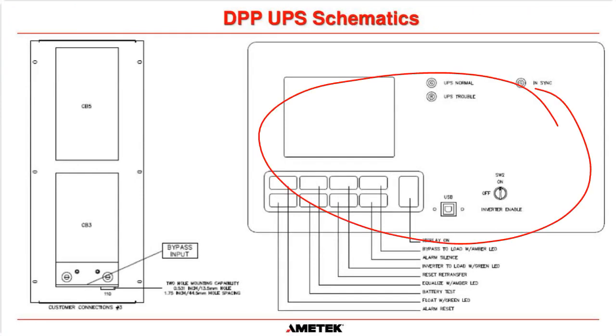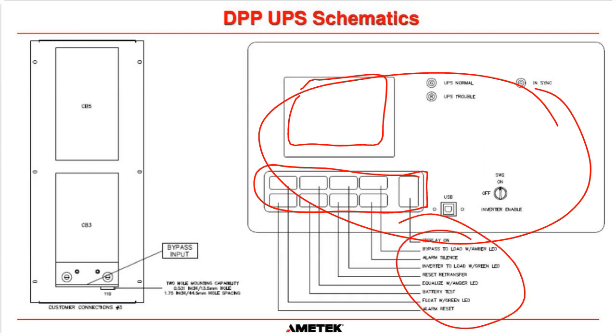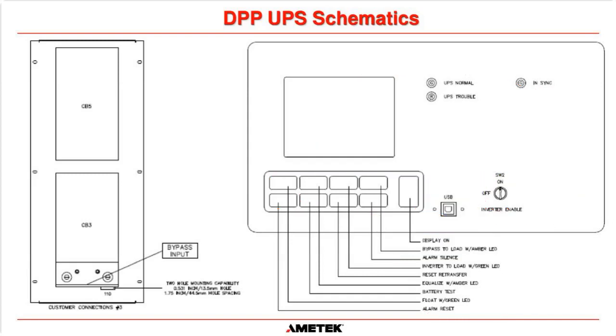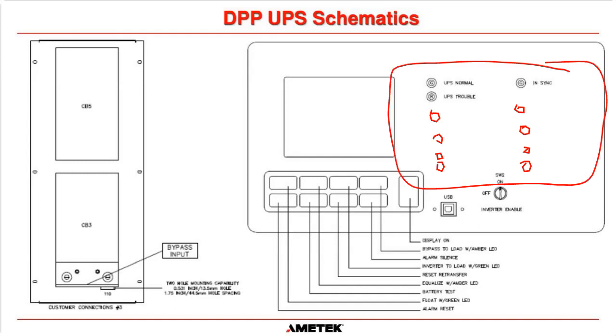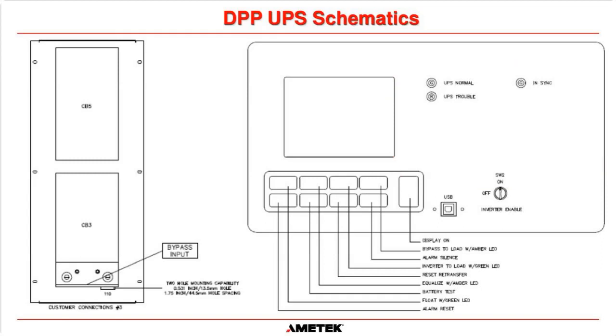And then we have our Mimic. Okay, this is now a touch screen. So you do all your interaction through the touch screen, and there are some push buttons on this keypad here as well. And it tells you down here what each of the buttons does. That is how you connect to our system using a computer and download alarm logs and details about the system. And this is the inverter on-off switch. If you remember previously, I said for the microfarad, it doesn't have an on-off switch, but for the DPP, we do have an on-off switch. And you can see here, on this system, we have 3 LEDs: a UPS normal, a UPS trouble, and an in sync. In truth, I think it's a row of 6, it could be more. Depending on what your design engineer bought, you can have many more LEDs on the front of your system. So once again, this is specific to the system that you bought using that serial number.